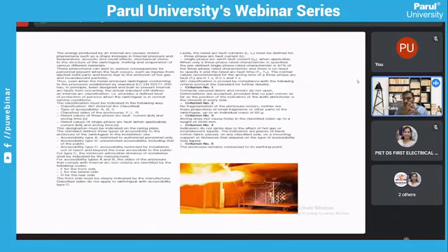Correctly secured doors and covers do not open. Deformations are accepted, provided that no part comes out as far as the position of an indicator, because there is a bit of a space gap. These indicators are sometimes thick cotton cloths, kept at a distance of 100 to 200 millimeter from the testing object. So part of the deformation is accepted, provided that nothing comes as far as the position of an indicator or the walls.